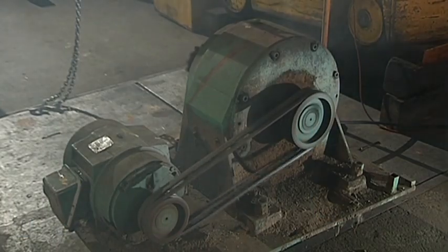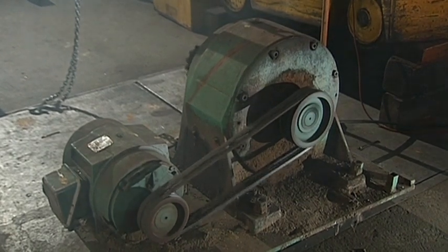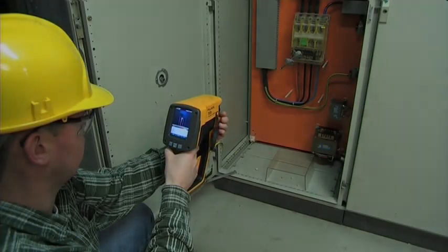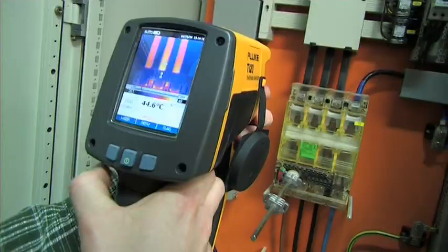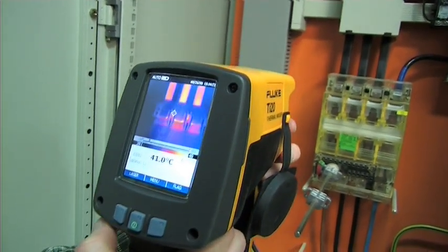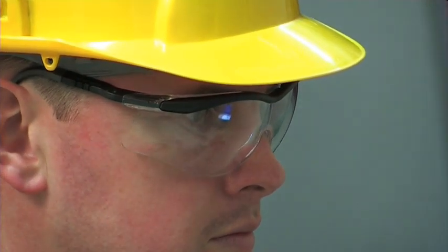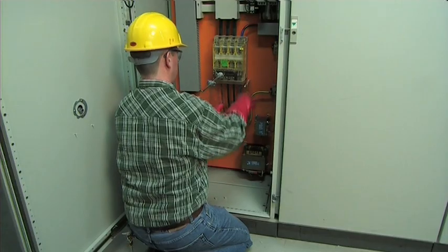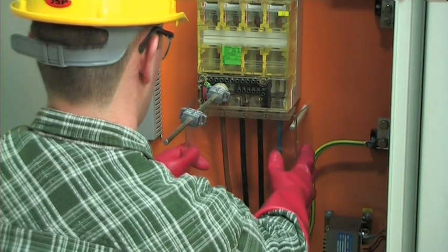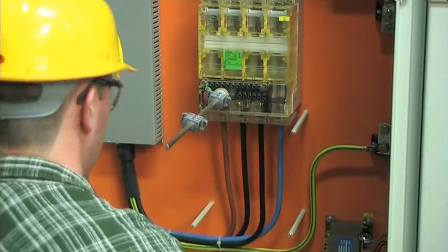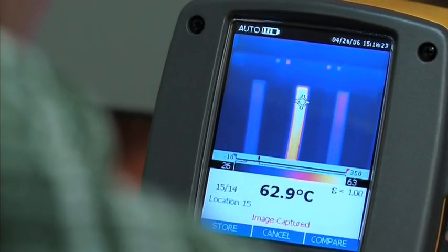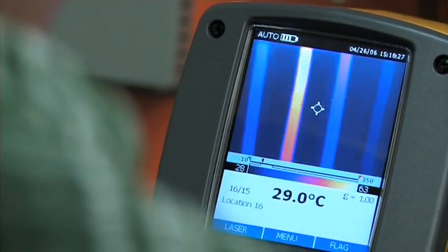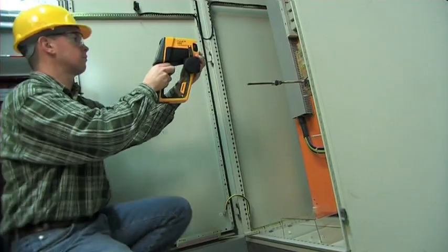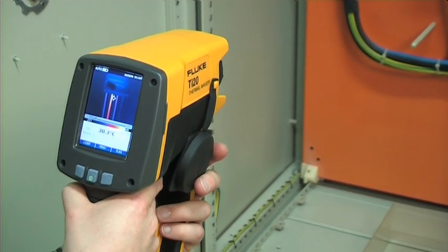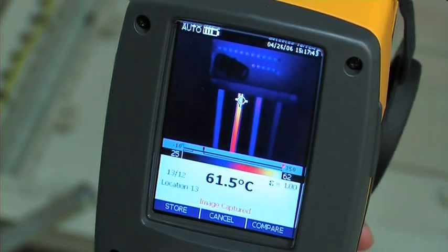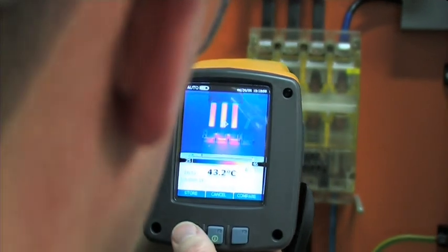Such power quality related problems could soon lead to a motor overheating and eventually breaking down, or an electrical short circuit bringing the risk of fire. When checking for power quality related problems, ensure you capture thermal images of all electrical panels and other high-load connection points such as drives, disconnects, and controls. Check panels and other connections with the covers off, using proper safety protection and practices. By capturing a thermal image of all three phases side by side, you can quickly spot temperature differences between the individual phases. Even a small difference of a few degrees Celsius should be further investigated. If the temperature difference between the phases is above 15 degrees Celsius, immediate action must be taken.